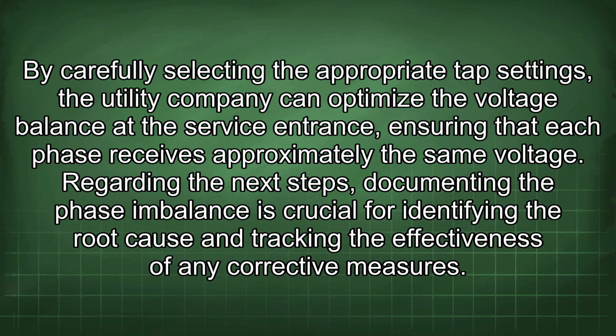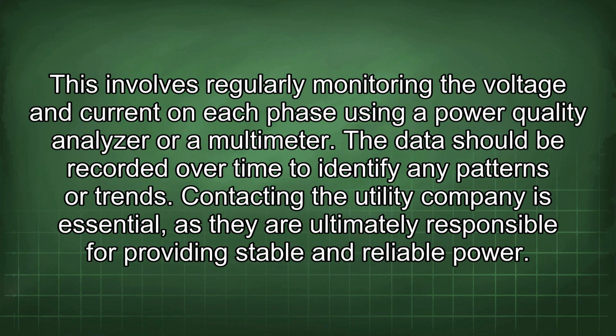Regarding the next steps, documenting the phase imbalance is crucial for identifying the root cause and tracking the effectiveness of any corrective measures. This involves regularly monitoring the voltage and current on each phase using a power quality analyzer or a multimeter. The data should be recorded over time to identify any patterns or trends.